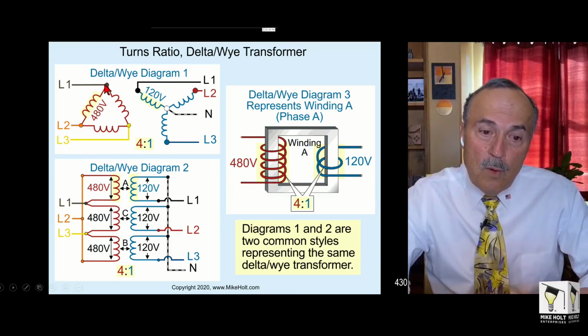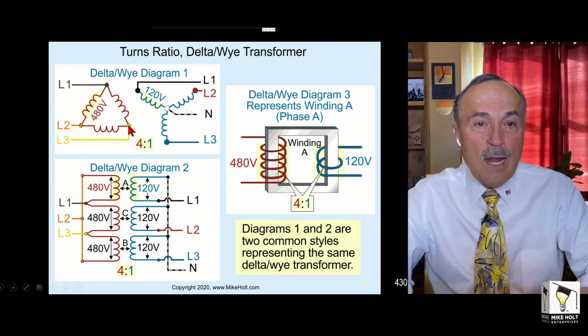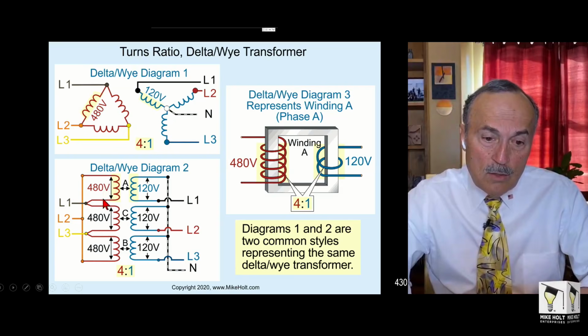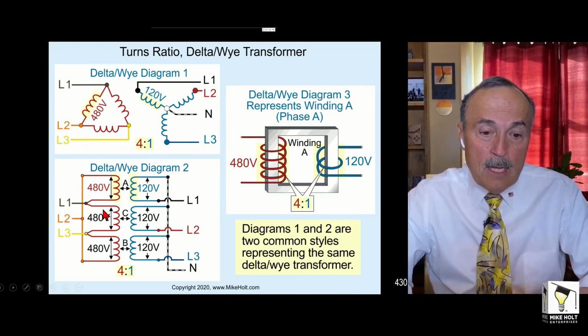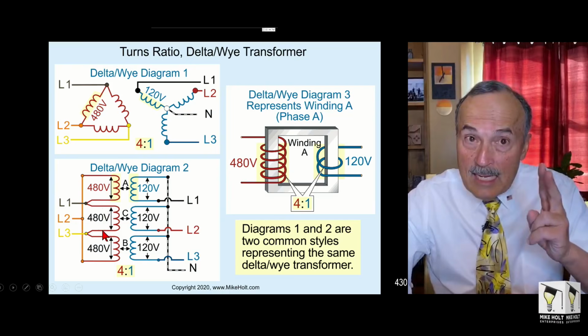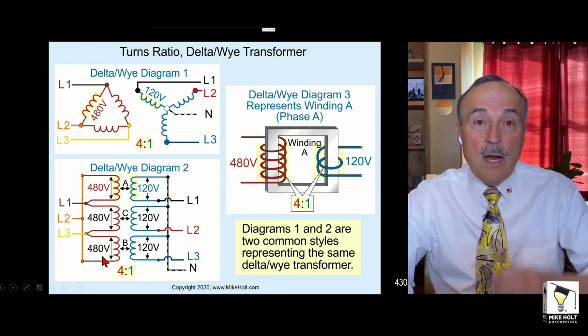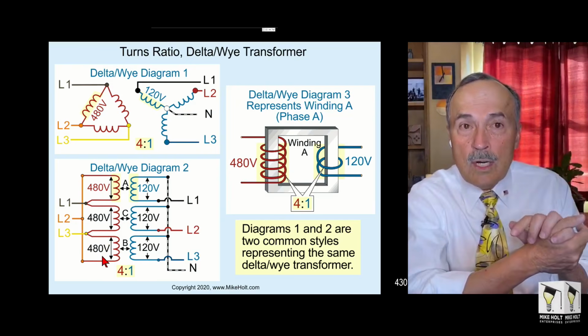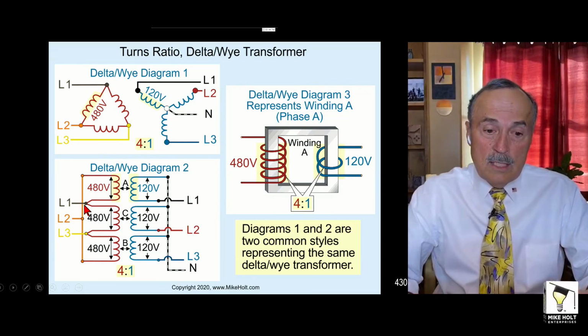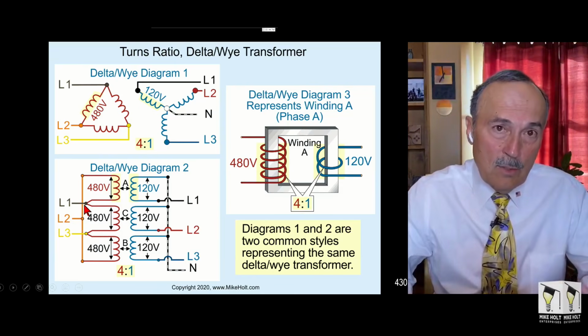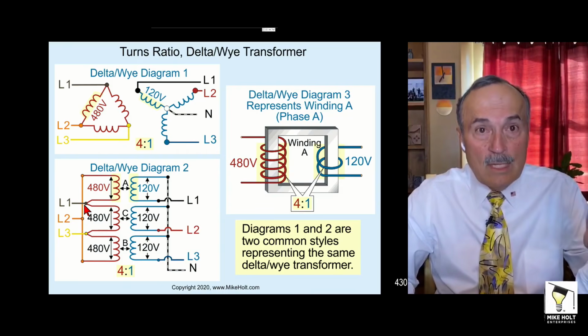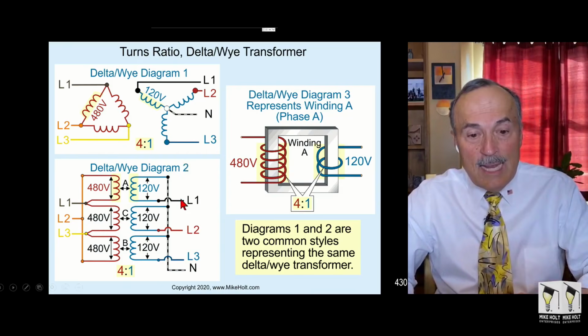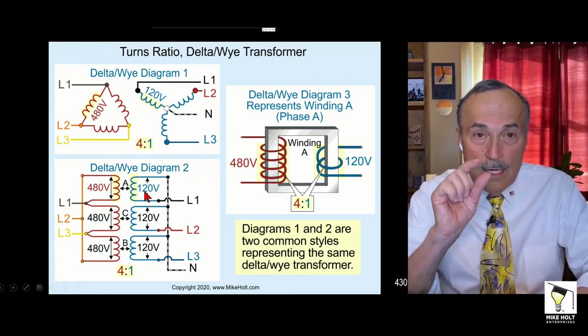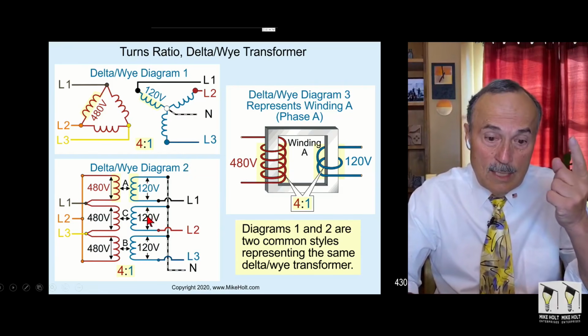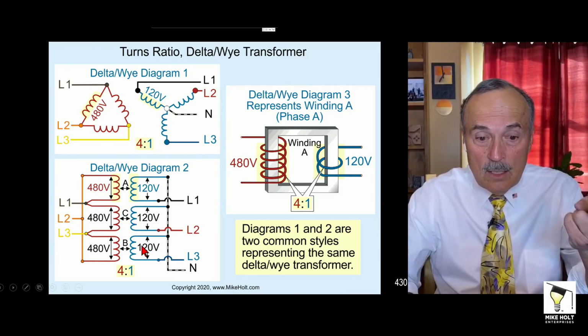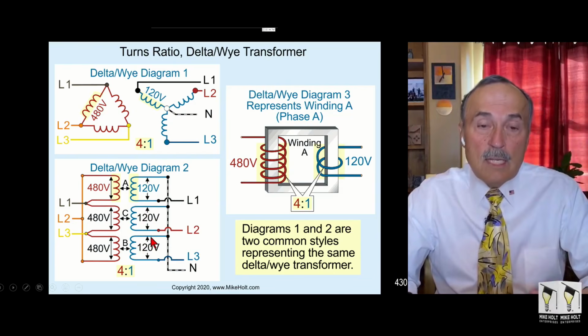And then, of course, we have points that are conductors coming in on the primary side. So here are the 2 wires on the primary of that one phase, here are the 2 wires on the primary of the second phase, and here are the 2 wires on the primary of the third phase, and this is all done internally in your transformer. All you're going to see is this terminal. It's not going to be L1, L2, L3; it's probably going to be H1, H2, and H3. And on the secondary, you're not going to see the 2 wires for each secondary winding. It's all going to be done internally.